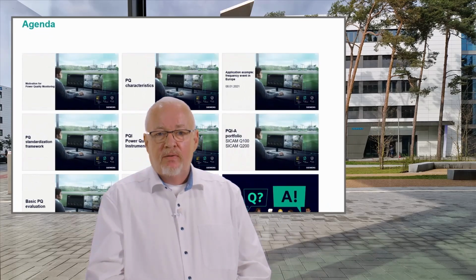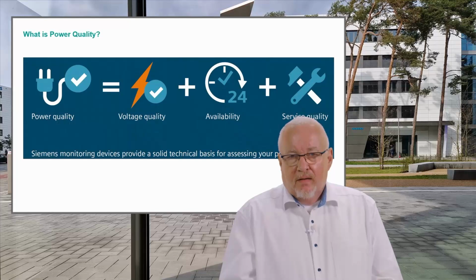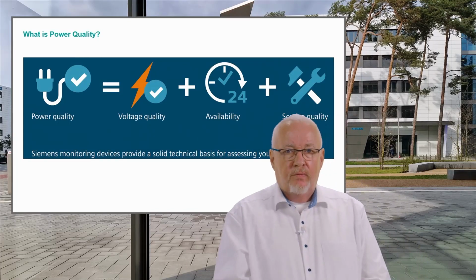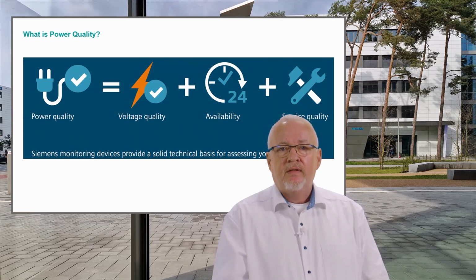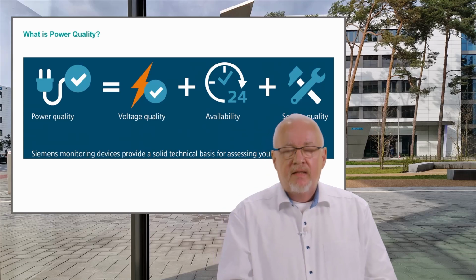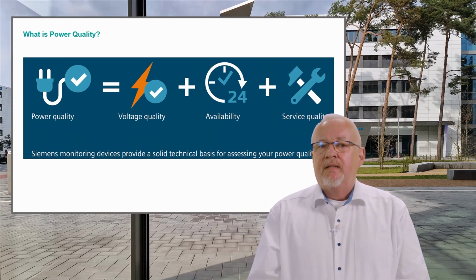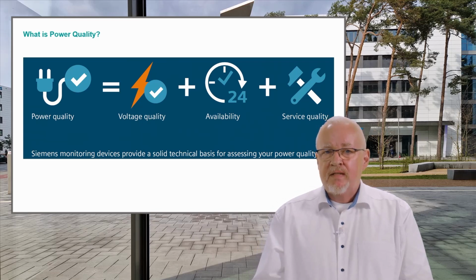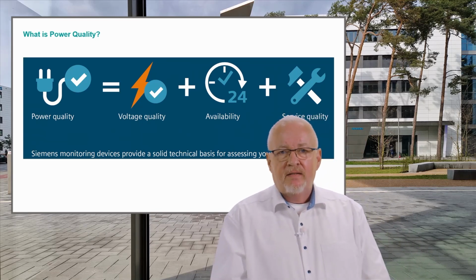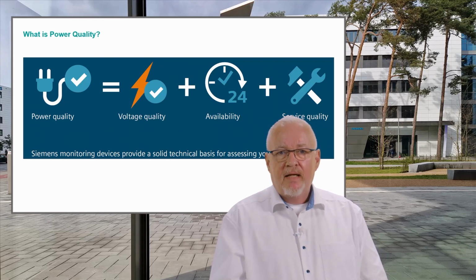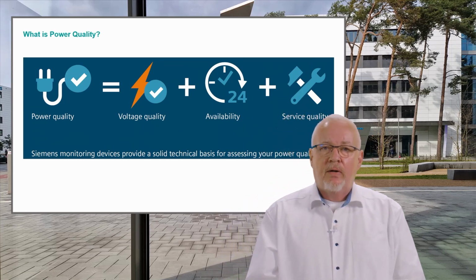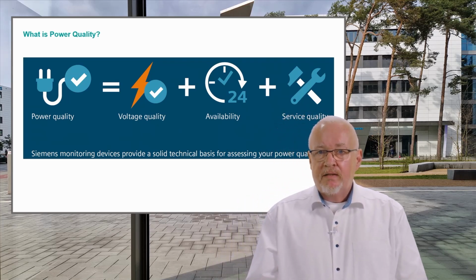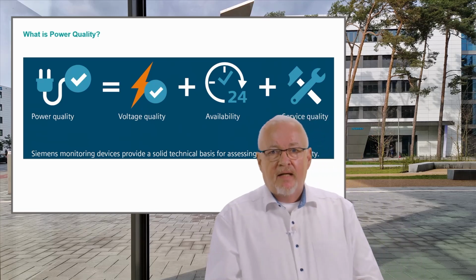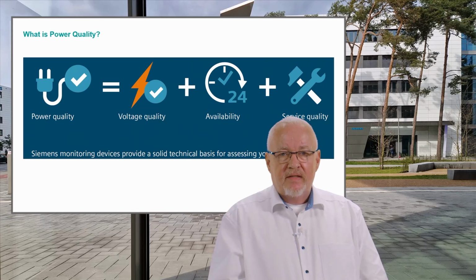At first, what is power quality? Power quality is the summary of voltage quality. In an ideal case, the voltage waveform is a pure sine wave. Nonlinear loads can disturb the voltage waveform, but these disturbances are limited by standards. The second part is the availability: 24 hours per day, 7 days per week, no voltage events. And the third part is the service quality. Is a continuous power quality monitoring installed, and are both sides, supply side and demand side, observing the compliance with limits?